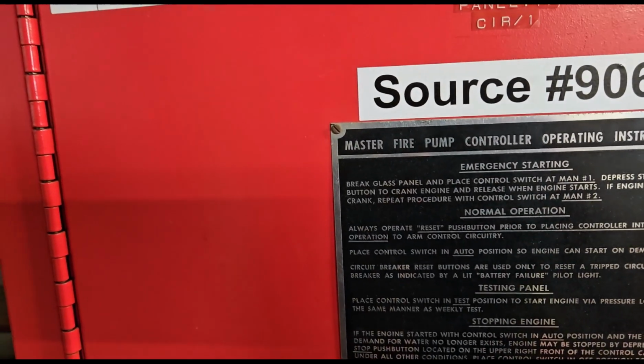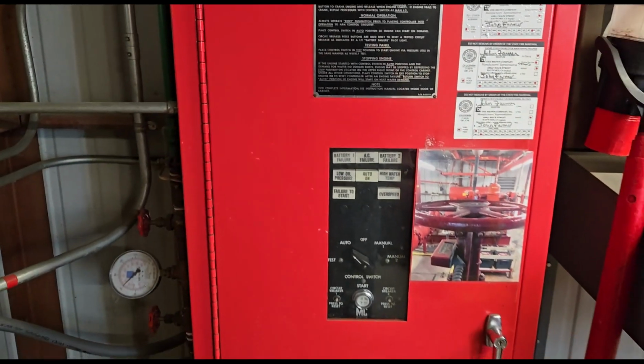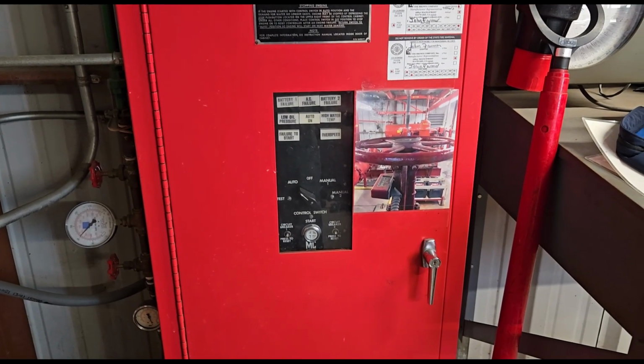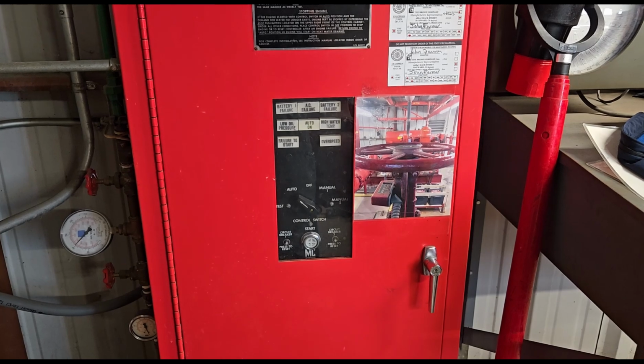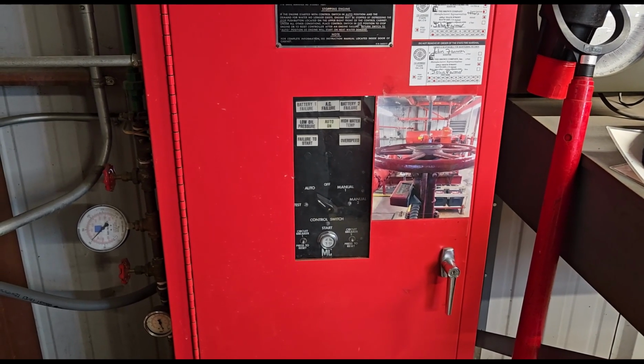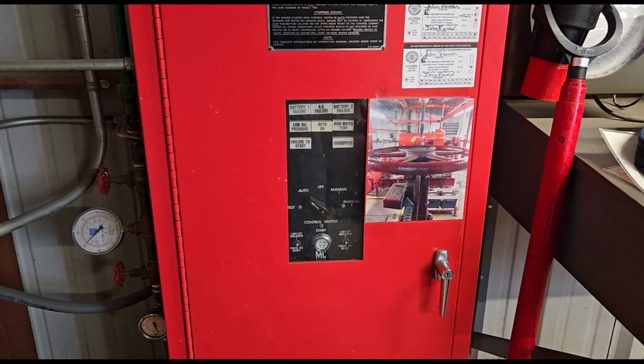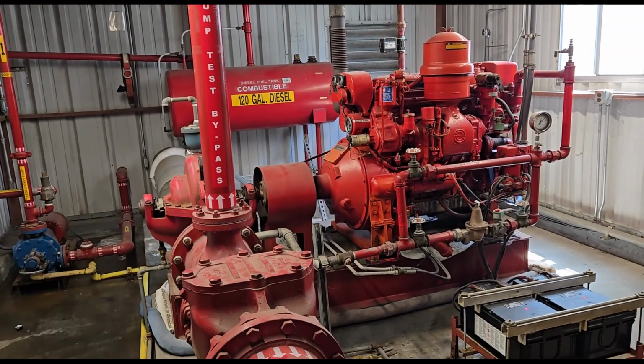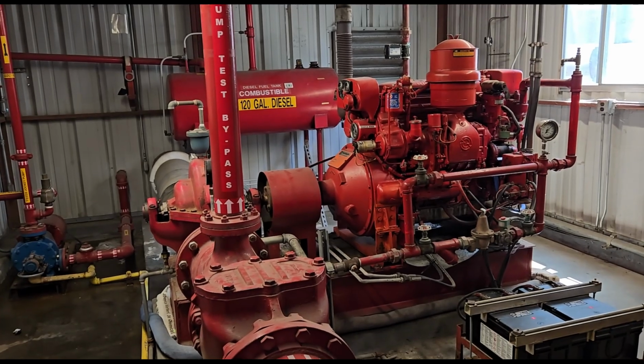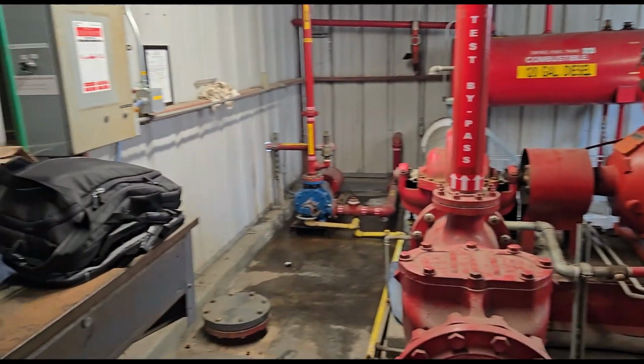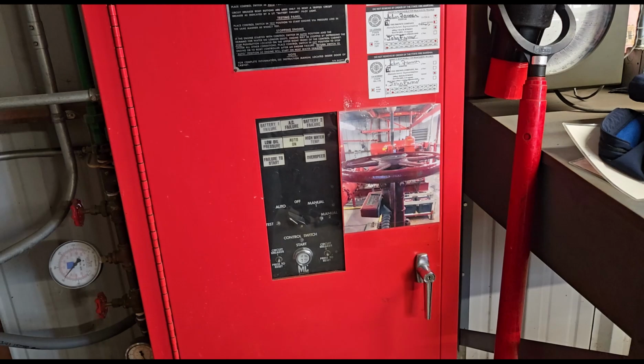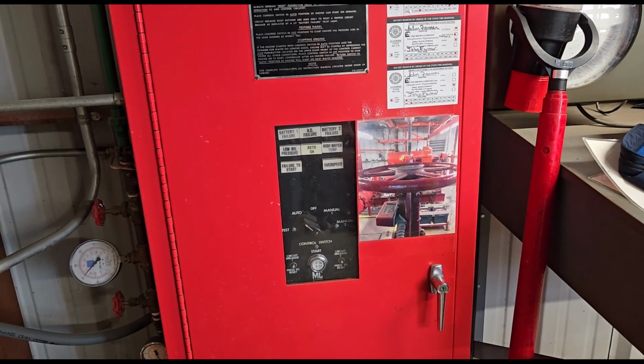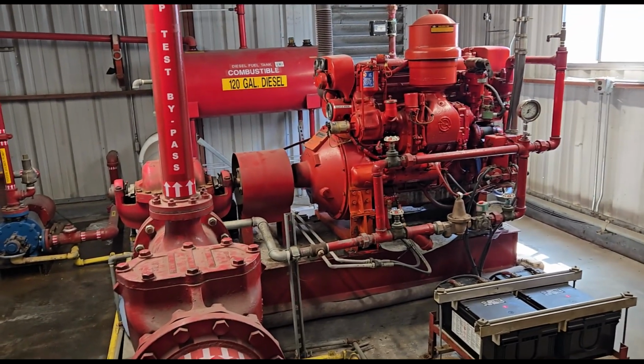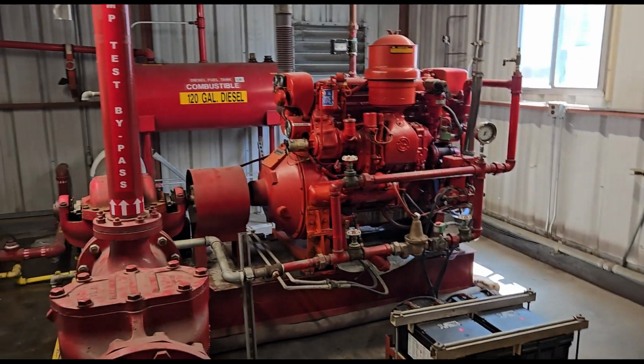Alright, so again, this is how you turn off the diesel fire pump so you can do your flow testing. Again, I'm an alarm technician. We have a separate sprinkler team that does the pump testing. They're the ones that come out and test the pump. I'm just testing the electronics, so the flow switches and tamper switches. So we just bypass the pump to make sure that it doesn't turn on, cause any issues, overpressurize the system, or heat up and ruin the packing or bearings or anything like that.